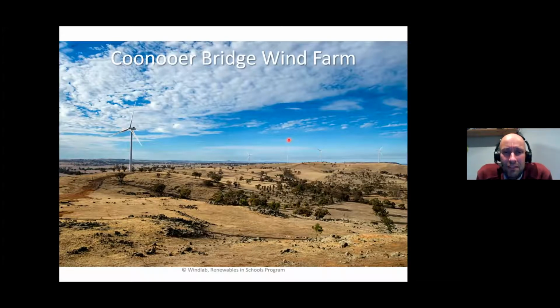When you describe the turbines feathering the blades, is this an independent action or controlled in some remote control room? It's an independent action. Every turbine has an instrument on top that measures wind speed, with a pre-programmed setting so that at a certain wind speed, the blades pitch to a certain angle. Automatically, when the wind gets above the cutout wind speed, it feathers the blades to shut down and protect against high wind speeds.